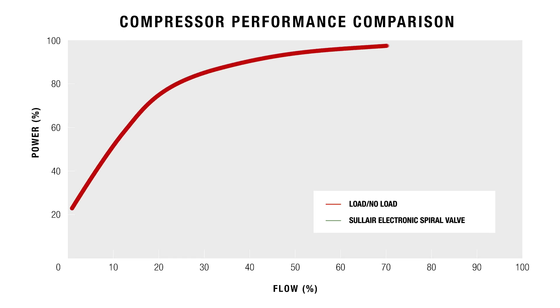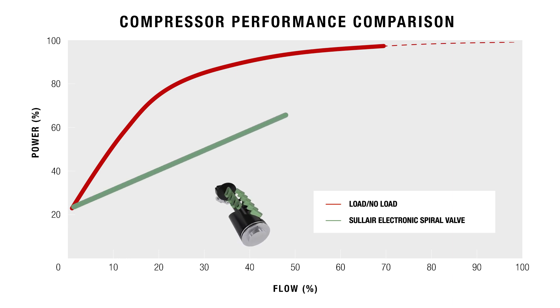When reloading, a load-no-load system fully loads to 100% power first, then backs down to current demand. Compressors featuring electronic spiral valve technology load to the effective capacity of the shortened compression chamber due to the still fully open bypass ports. Then, the turning spiral valve will gradually close the bypass ports until the compressor reaches current demand. This results in less strain and wear on the air end and associated components.